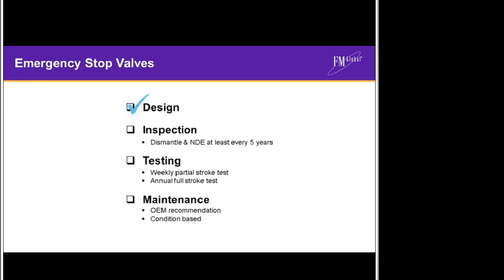When it comes to inspection, provided all risks have been minimized on the turbine, FM Global recommends a full internal inspection at no more than a 5-yearly interval. However, if there are relevant deficiencies, such as water chemistry excursions or intermittent testing histories, a higher frequency would be recommended. With regard to testing, the predominant failure mode is a sticking valve which fails to close properly. This is often a consequence of poor water chemistry, but mechanical failure and other factors cannot be discounted.